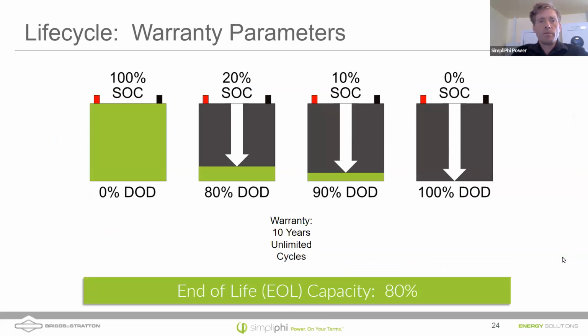Let's talk a little bit about cycle life. Daniel, if you were sizing a system just for typical battery backup, what depth of discharge would you choose? Well, if I had a battery that I knew was just sitting there waiting for an outage, I would probably size the system to use all 100% of that battery.